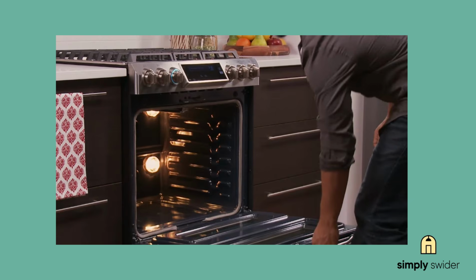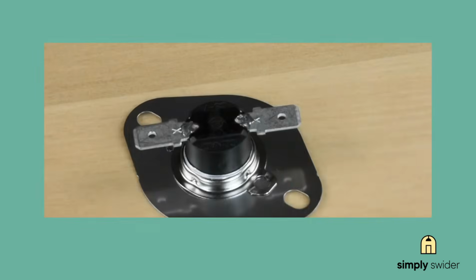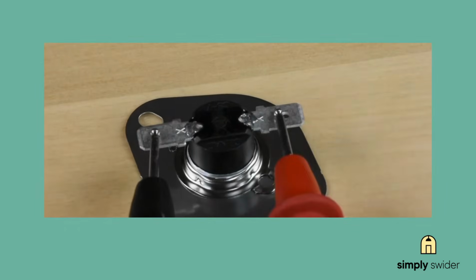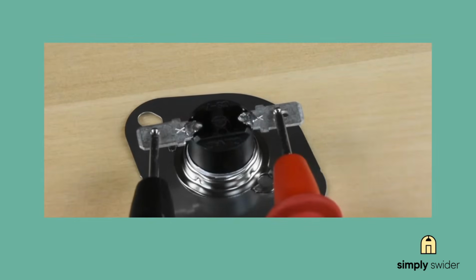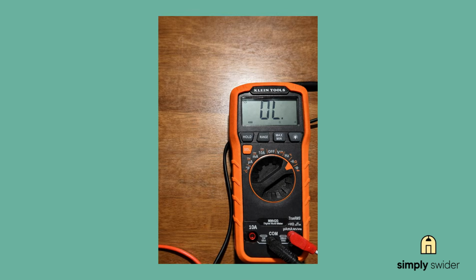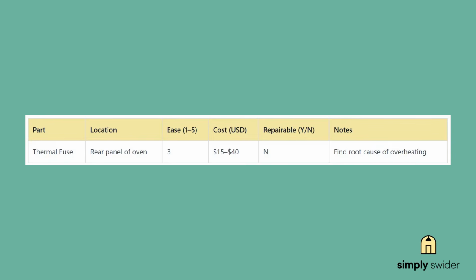It's located on the back of the unit, and testing it is simple. Just check for continuity with your multimeter. If the circuit's open, it's tripped. Some are resettable, most are one-time fuses that you got to replace. They're cheap, usually 15 to 40 bucks, but you do need to access the back panel. Here's the thing though. Don't just replace it and call it good. Figure out why it tripped in the first place or you'll be right back where you started.